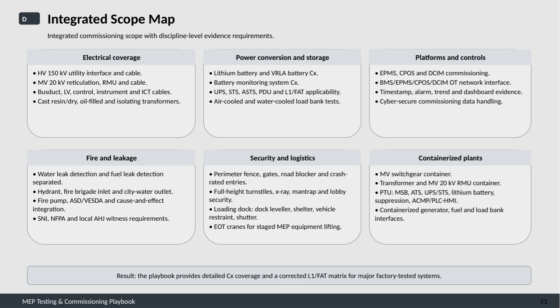Security and logistics address perimeter and access controls, such as fences, gates, road blockers, crash-rated entries, turnstiles, and screening devices including X-ray and man-traps. Loading dock equipment is also included for safety and logistic support, as well as use of overhead cranes for equipment installation. Lastly, containerized plants cover commissioning of modular container units housing medium-voltage switchgear, transformers, control and power distribution systems, generators, fuel systems, and load banks. The overall result is a detailed commissioning playbook that provides extensive coverage and includes a corrected Level 1 and factory acceptance test matrix tailored to major factory-tested systems, ensuring quality and consistency throughout the commissioning process.